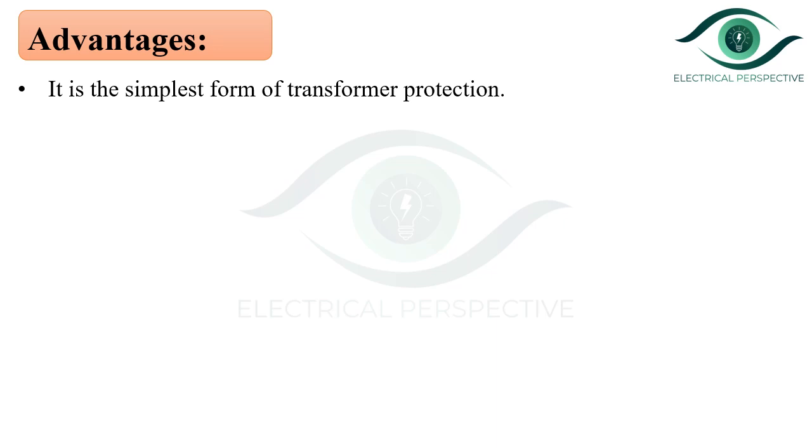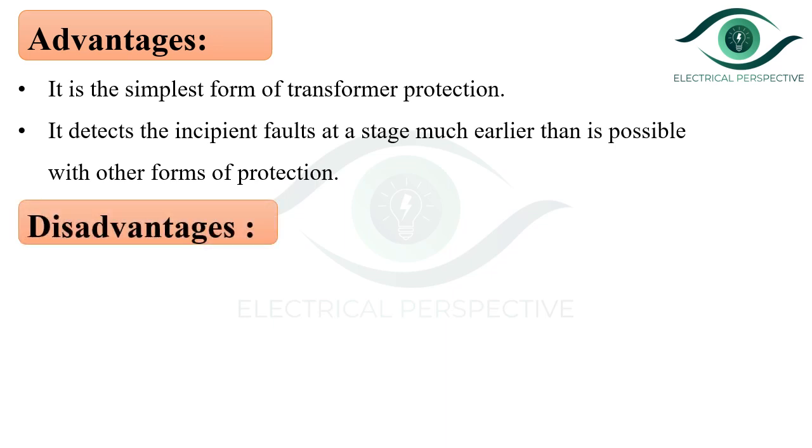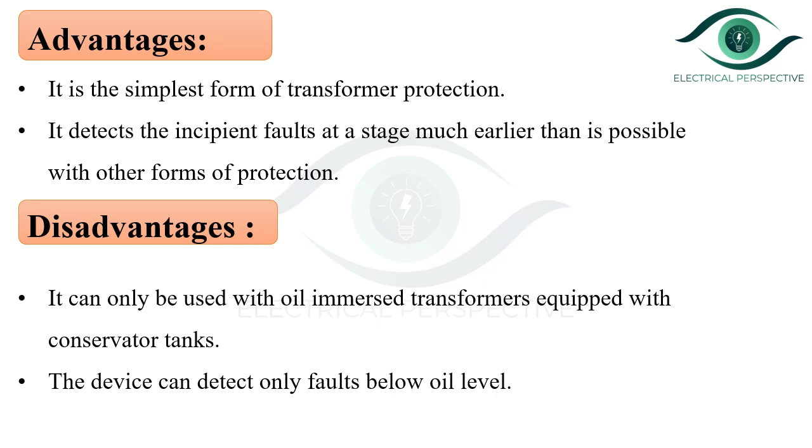The advantages of Buchholz relay: it is the simplest form of transformer protection, and it detects incipient faults at a stage much earlier than is possible with other forms of protection. The disadvantages: it can only be used with oil-immersed transformers equipped with conservator tanks, and the device can detect only faults below the oil level.